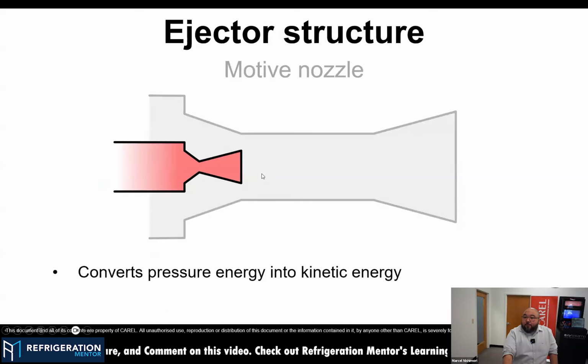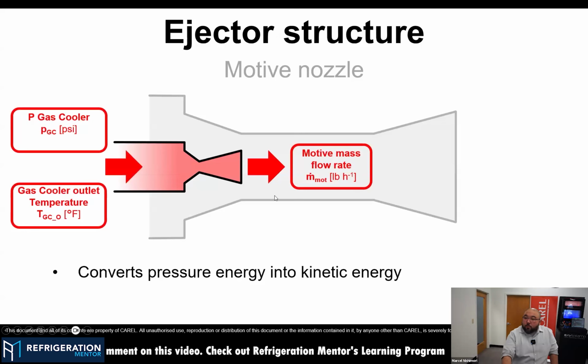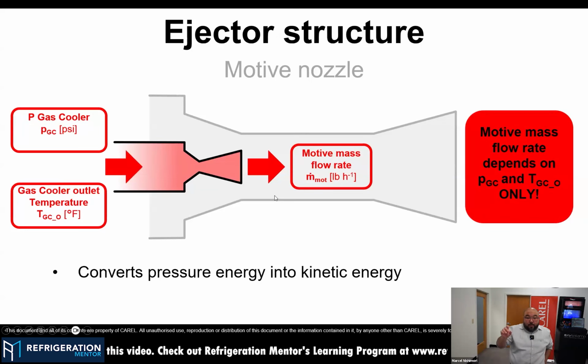So coming internally, I have divided this presentation in a couple of parts. Thinking about the motive, or the gas cooler pressure, the inlet from the gas cooler, we have a higher pressure, normally during summer conditions or warm ambient or heat pump application, with a certain gas cooler outlet temperature. The main function of the ejector will be regulating that pressure, acting as an HPV valve. So in the case of CAREL ejectors, we can totally replace the HPV valve with an ejector. You don't need to have two different components, mainly because the ejector is able to control the pressure on the gas cooler.